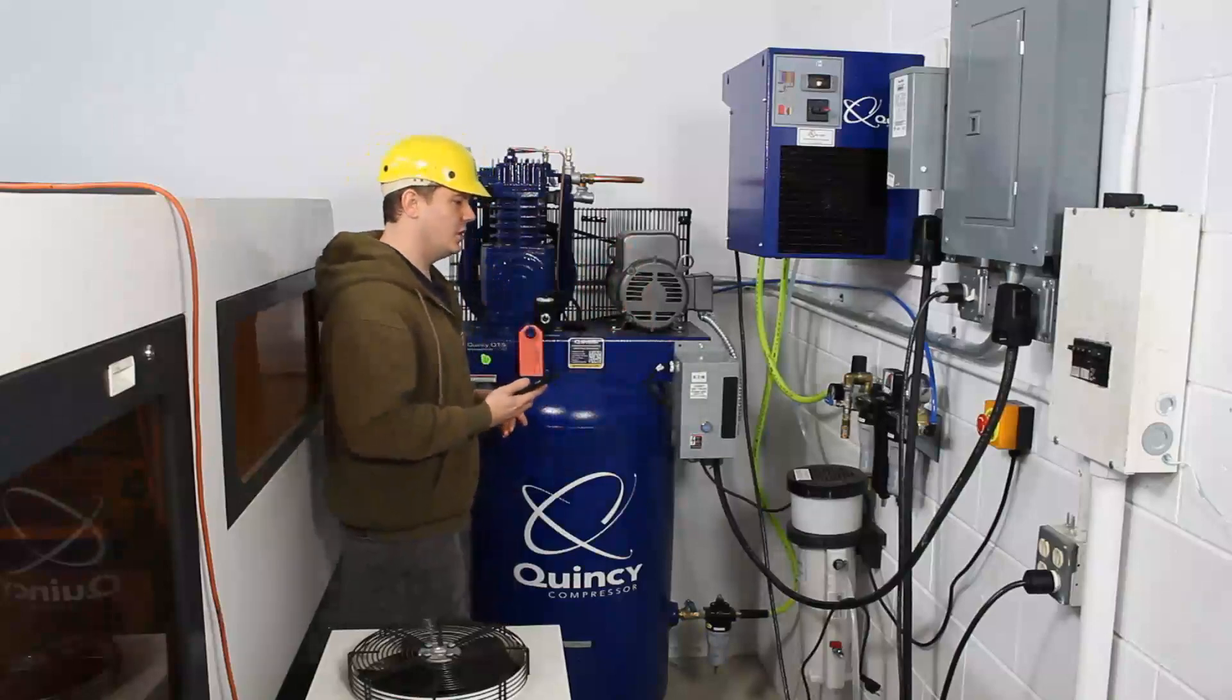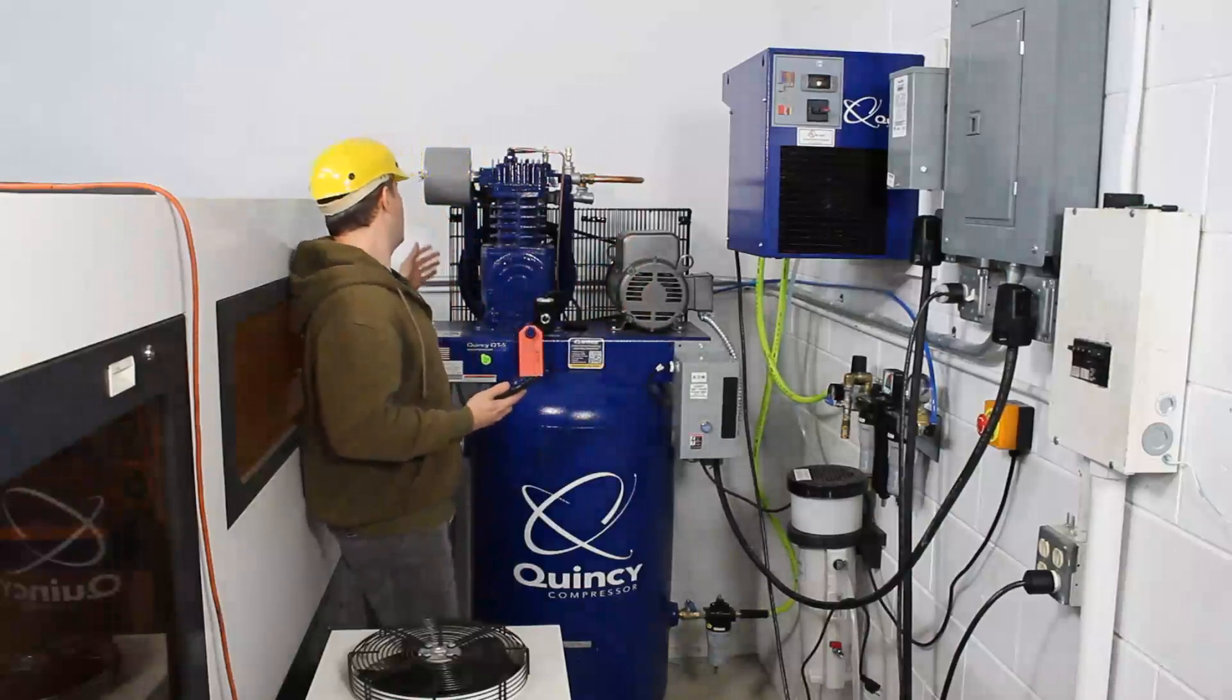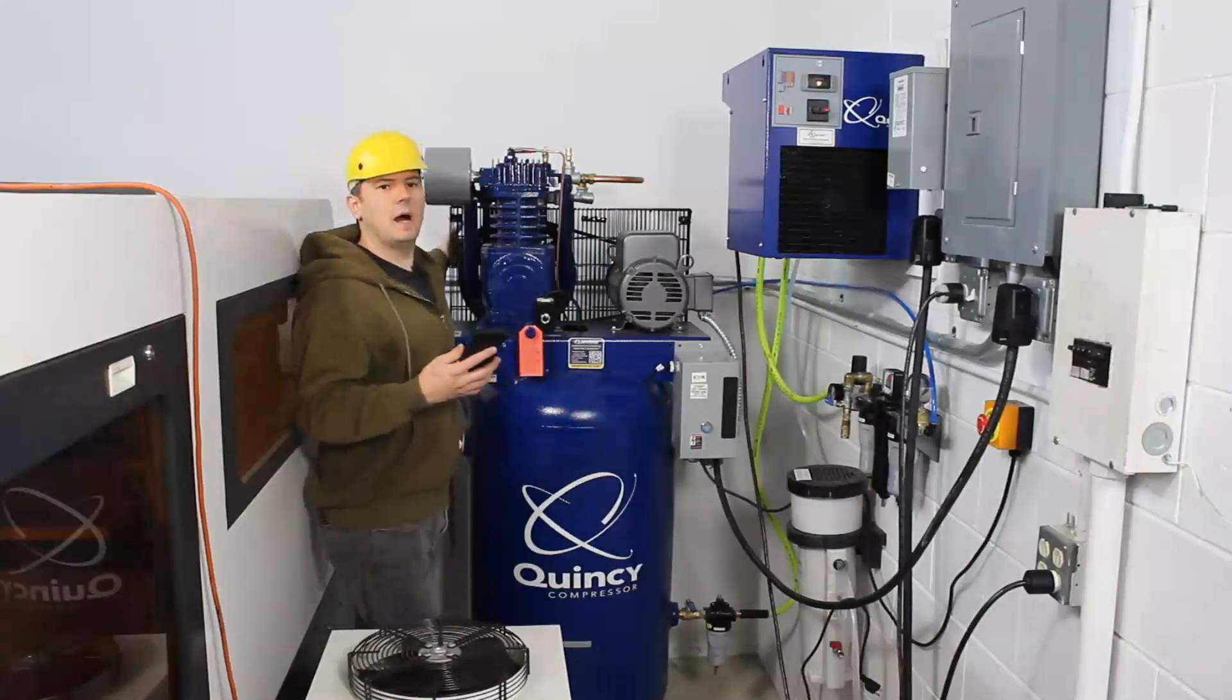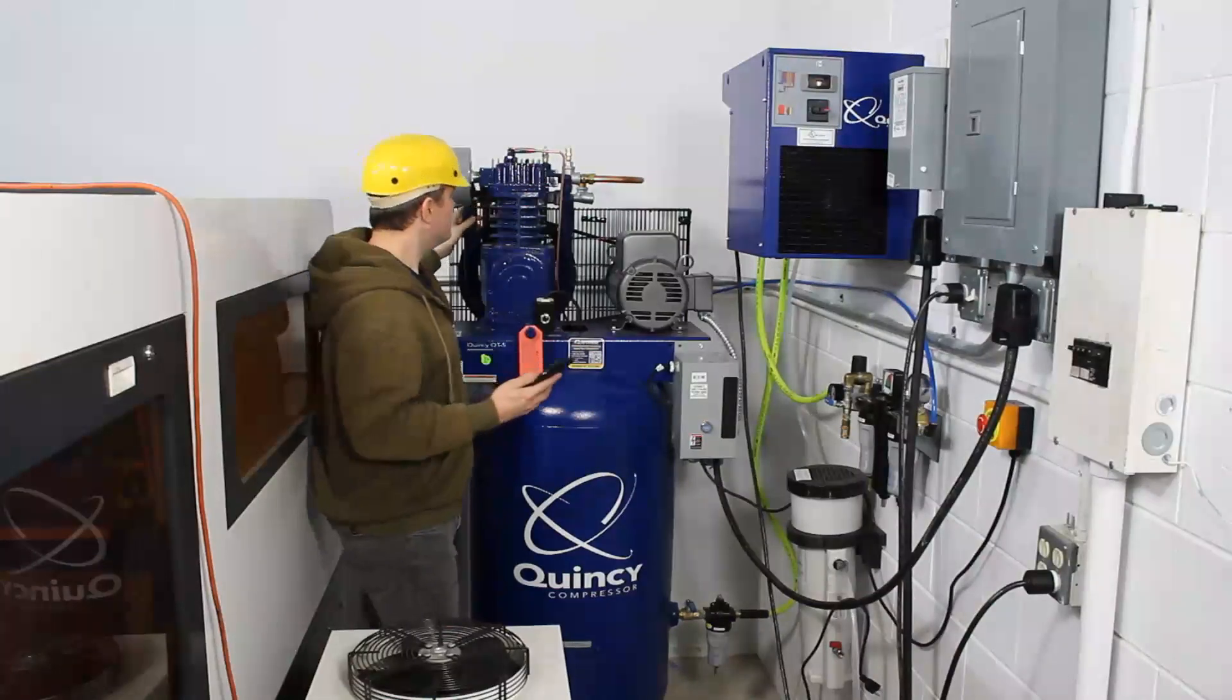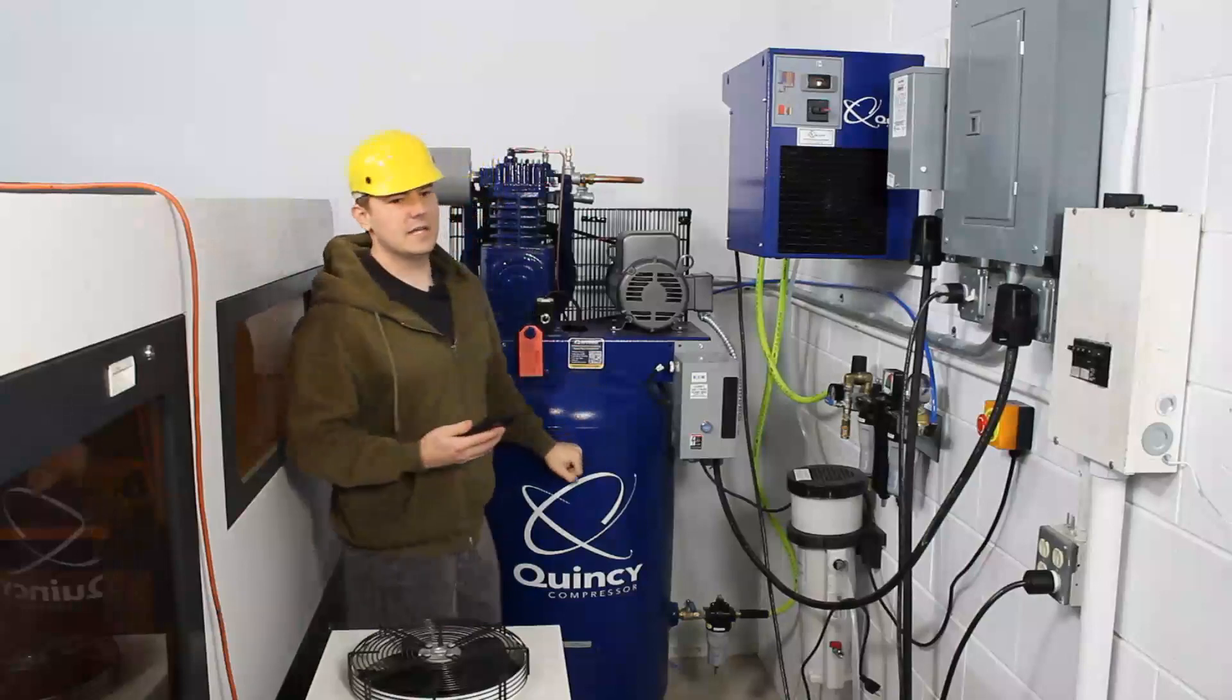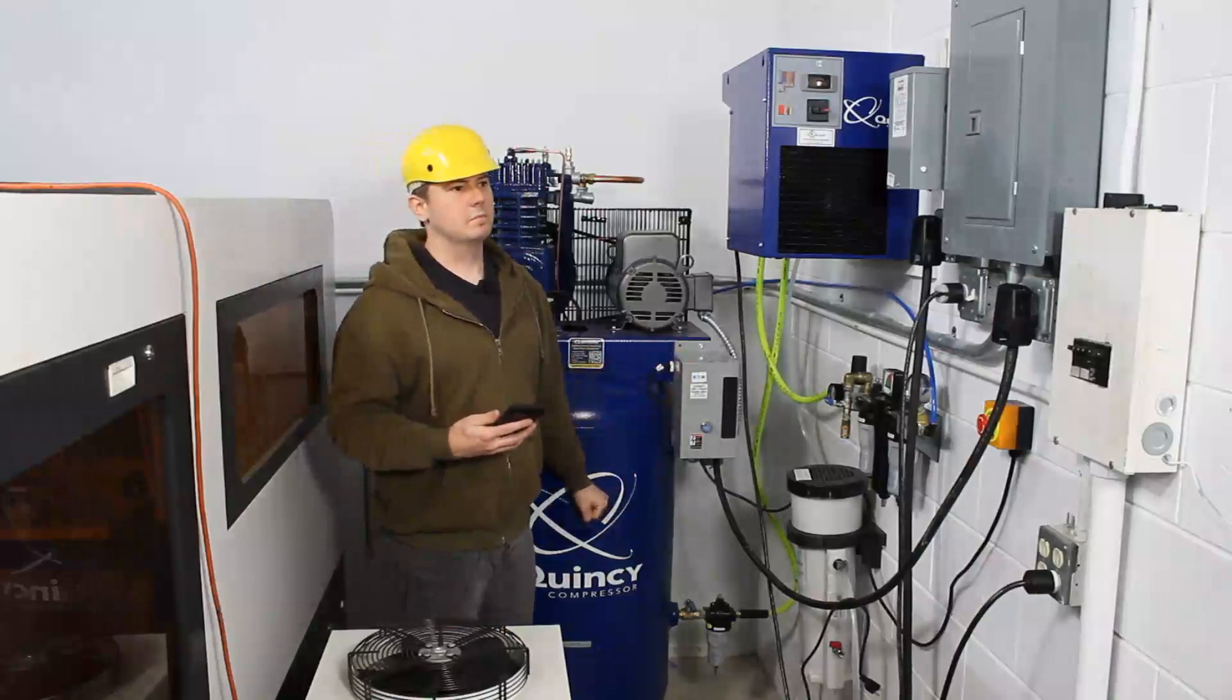So some of the additional add-ons that we did that we do feel is necessary, we have an intercooler behind. You probably can't quite see it. It's a radiator unit that pre-cools the air right after compression. This is the 80 gallon tank model. I would not recommend going any smaller, you want to have a nice big tank.